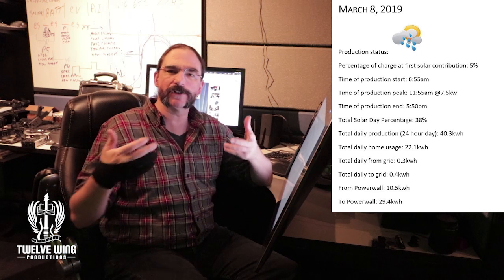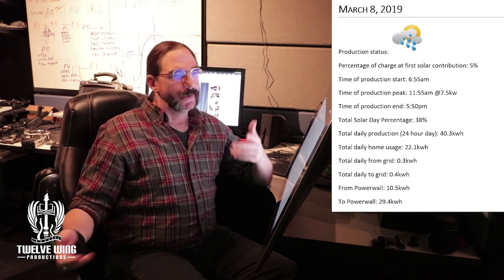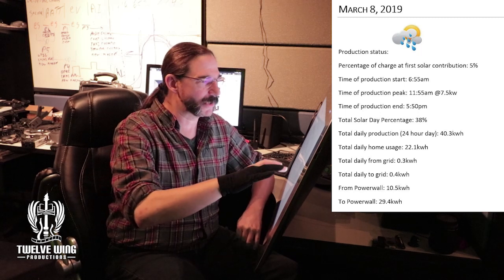We covered that even though there's that built-in reserve on the battery so that they don't fully deplete, you still would like to keep the system topped off a little bit higher. And we'll discuss that later as we start to go into the summer months, where we may start to make those decisions to turn off a few of the batteries if we don't need them, and then force the majority of the rest of the system to operate higher instead of running the risk of having those things nearly fully charged all the time. So we'll kind of go with that as we come across it.